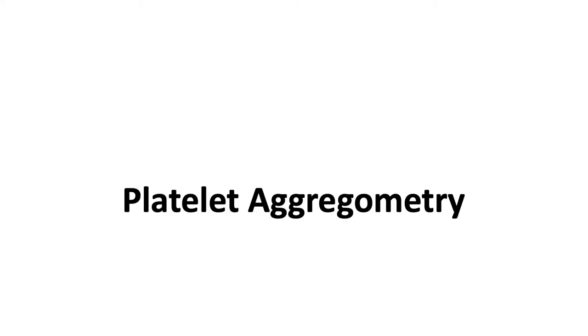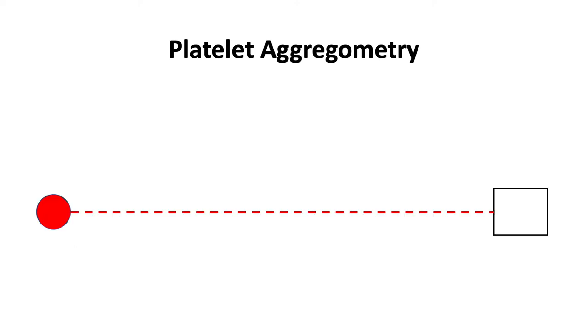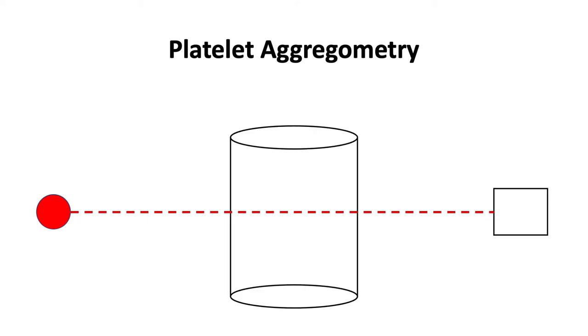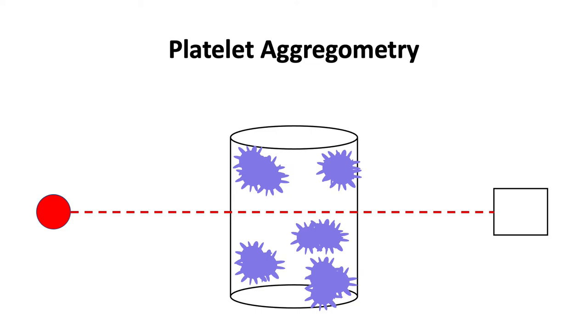We test this process in the lab using platelet aggregometry. Platelet aggregometry makes use of a light source which emits light that is measured by a detector. Between the light and the detector is placed a clear container filled with a suspension of platelet-rich plasma. Light does not pass through to the detector until an agonist is added, beginning the process of platelet aggregation. The resulting light transmission is detected and recorded as a function of time. The data is shown as a graph with percent aggregation on the y-axis and time in seconds on the x-axis.